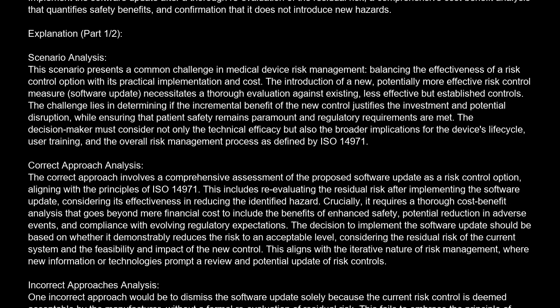One incorrect approach would be to dismiss the software update solely because the current risk control is deemed acceptable by the manufacturer, without a formal re-evaluation of residual risk. This fails to embrace the principle of continuous improvement inherent in risk management and ISO 14971, which encourages seeking more effective risk reduction measures.